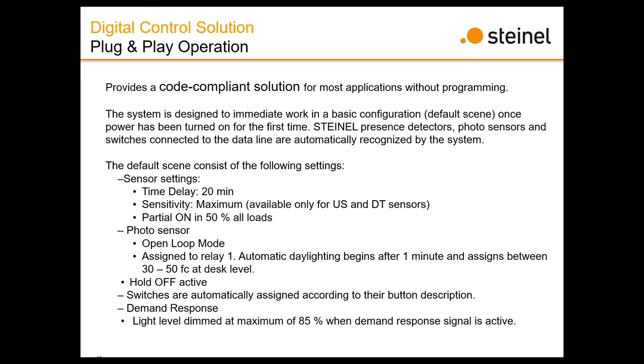The system automatically recognizes what's connected to it. For example, if you connect an occupancy sensor, it recognizes that and puts it at a preset level. We set it for a 20-minute time delay. If it's an ultrasonic sensor or a dual tech sensor, we put the sensitivity at maximum, and set it for partial on at 50%. Now you can change these things afterwards, but this is the preset.